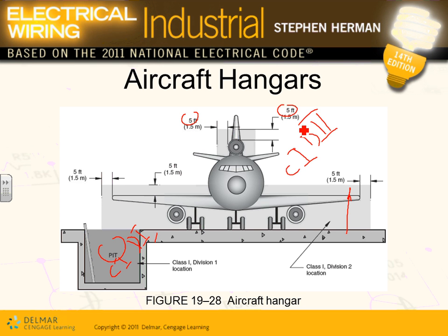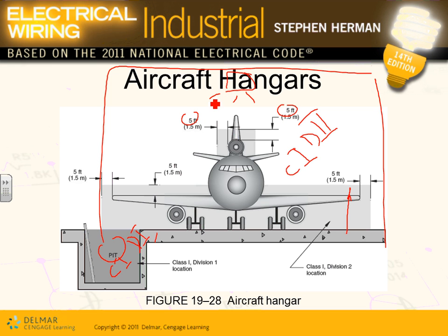So when you design a system for aircraft hangars, your equipment has to clear all your fixtures. Here's my hangar here. You're going to put your fixture right here. That fixture, by the way, has to be enclosed, because if it falls here and there's a spill of jet fuel, bam, you've got yourself an explosion. So it has to be a special type of fixture, not explosion proof, but enclosed. And when you put all your equipment, you typically put it higher, your receptacles, so they don't have to be explosion proof. So class 1 div 2.